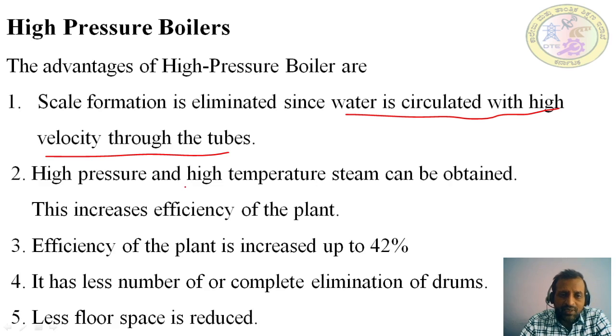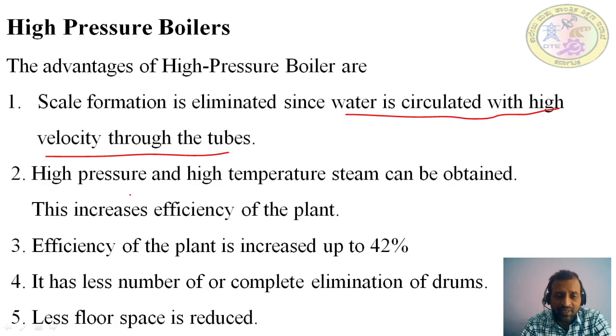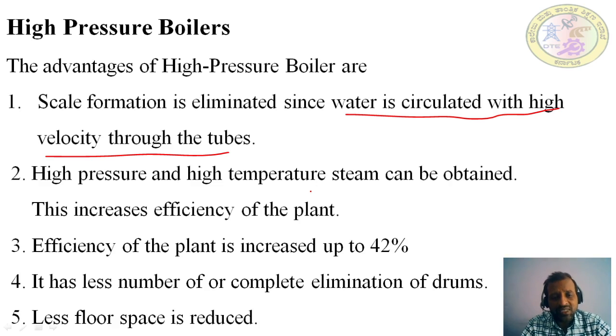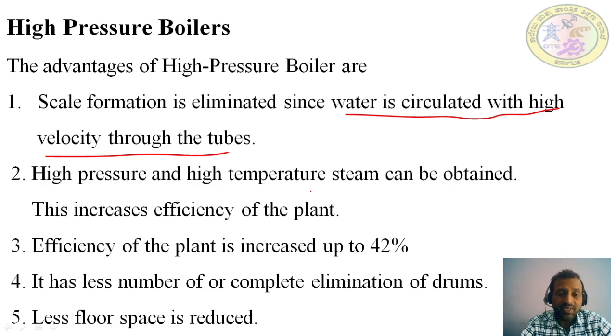Another advantage: high pressure and high temperature steam can be obtained, which increases the efficiency of the plant. Water is sent into the boiler at high pressure, and when the pressure is high, the temperature is also high. When the inlet water temperature itself is high, the steam produced at the end of the boiler is superheated steam, thereby increasing the efficiency of the power plant.